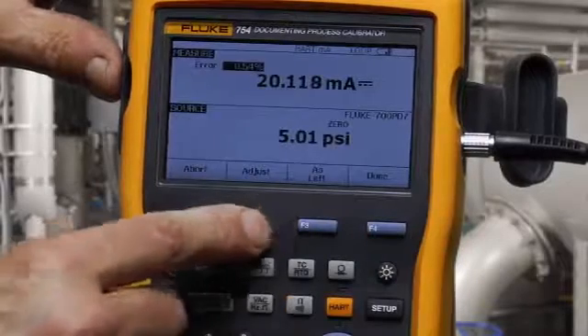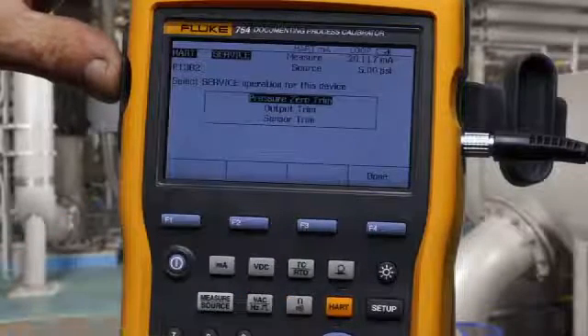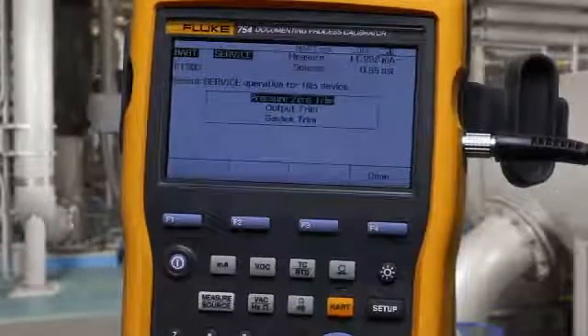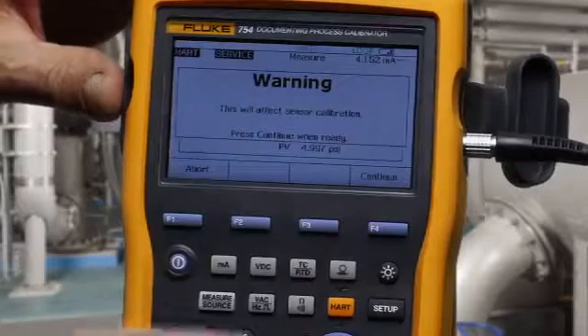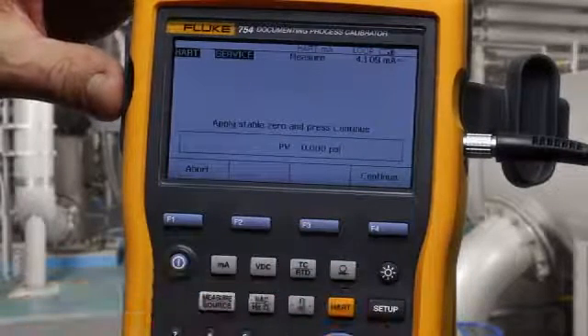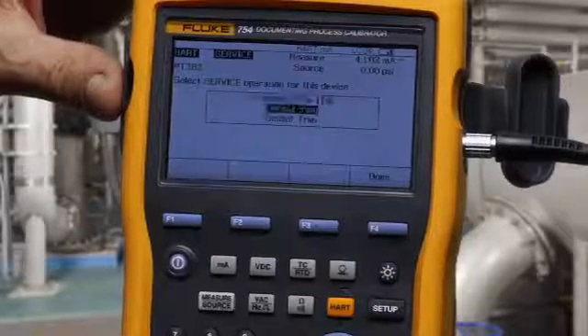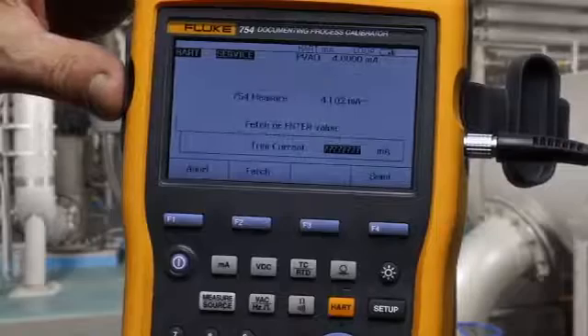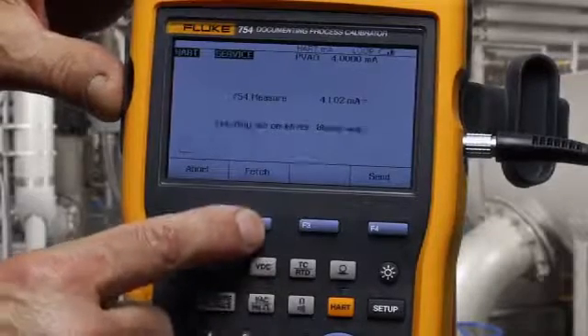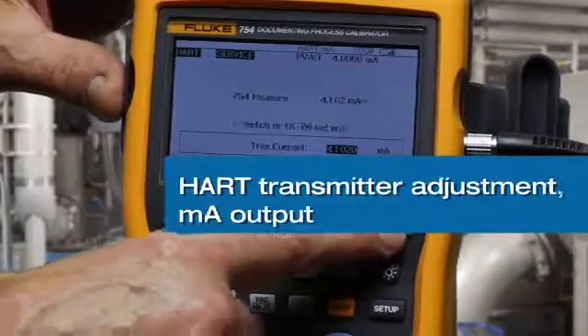Next select adjust. The first form of pressure zero trim. With the pump vented to the atmosphere. And then an output trim, where we trim the milliamp output by fetching a 4 milliamp value as measured and send the trim to adjust.